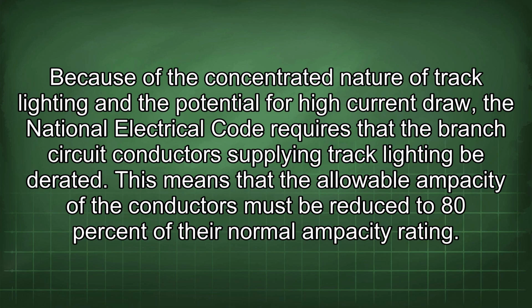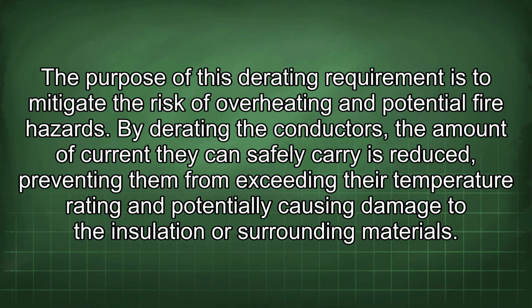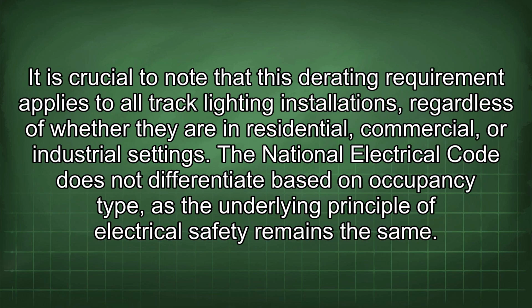This means that the allowable ampacity of the conductors must be reduced to 80% of their normal ampacity rating. The purpose of this derating requirement is to mitigate the risk of overheating and potential fire hazards. By derating the conductors, the amount of current they can safely carry is reduced, preventing them from exceeding their temperature rating and potentially causing damage to the insulation or surrounding materials. It is crucial to note that this derating requirement applies to all track lighting installations, regardless of whether they are in residential, commercial, or industrial settings.